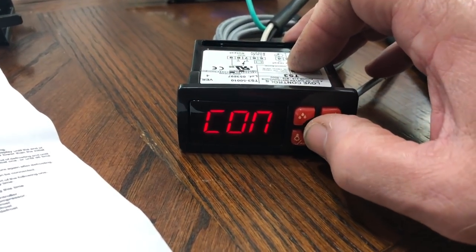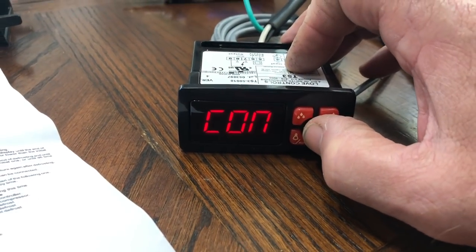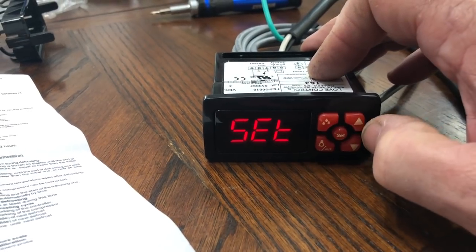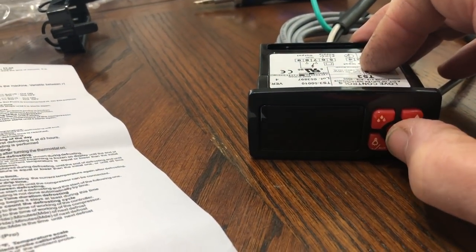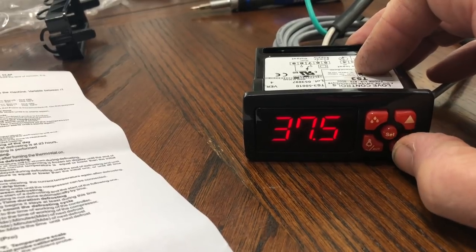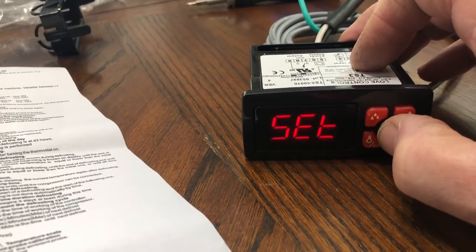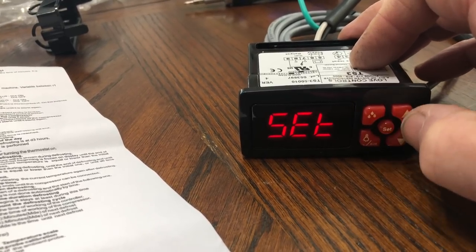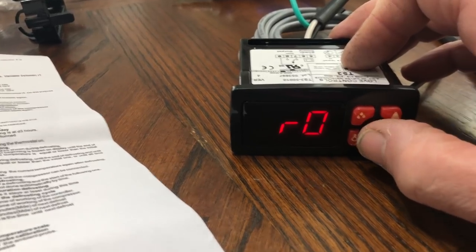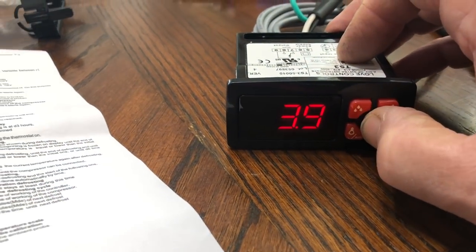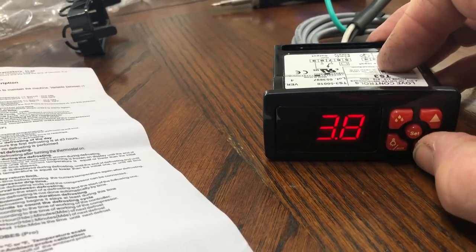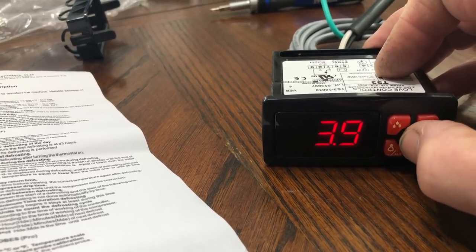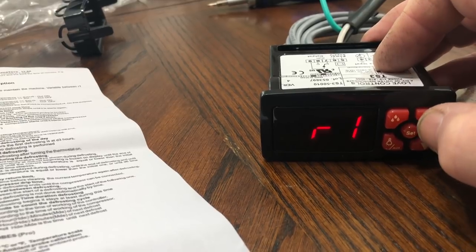So the CON descriptions. First one will be our set point. And I've already set it to 37.5 degrees. You can change it by going up or down. So we go back to set and then go up. RO is our differential. I got it at 3.8 degrees. You can change it by going up or down.